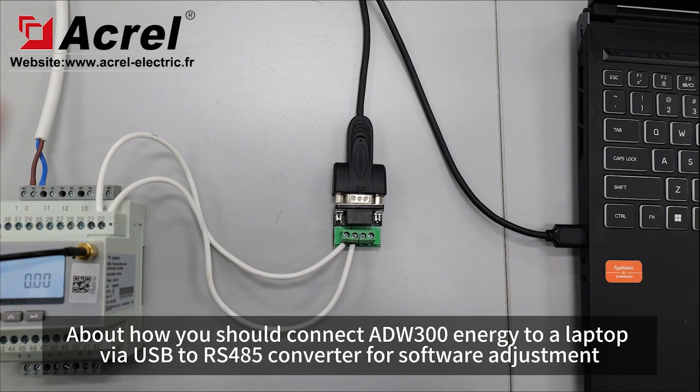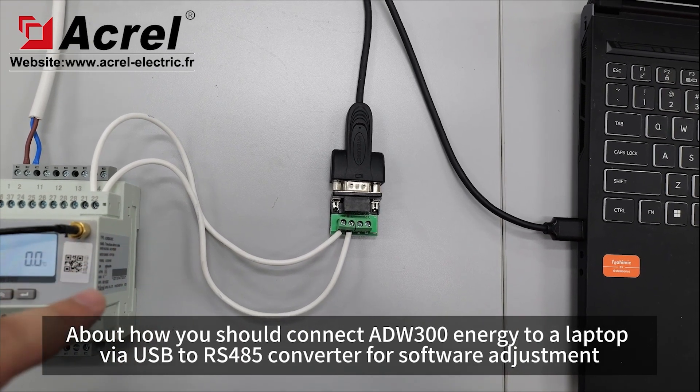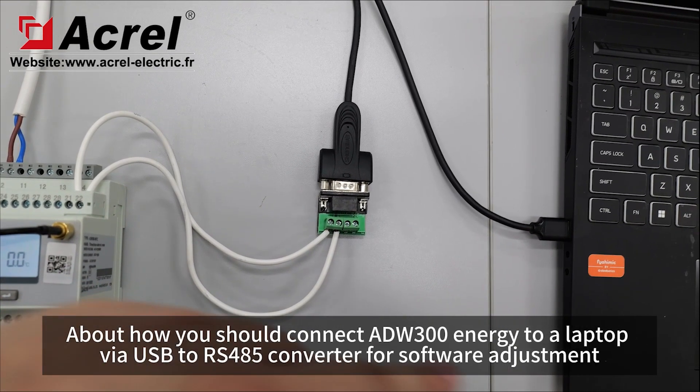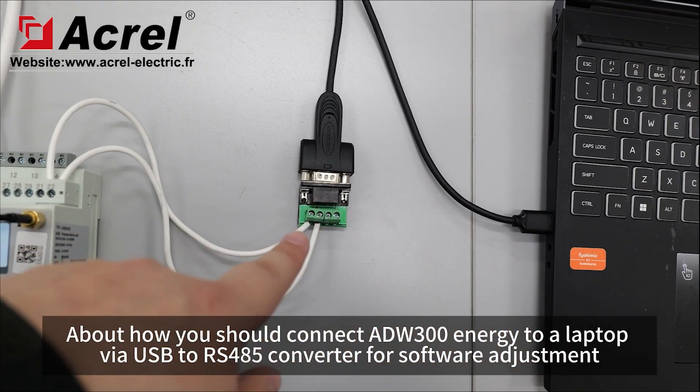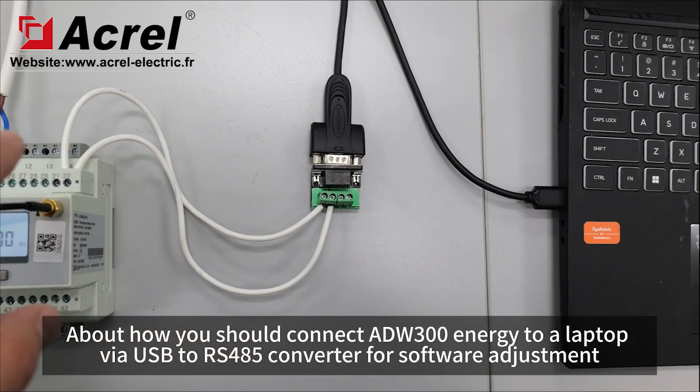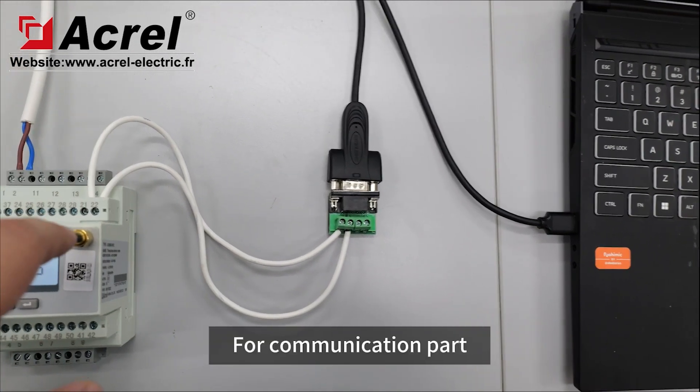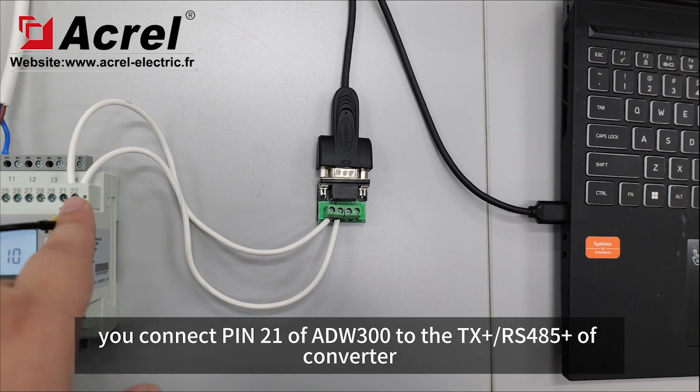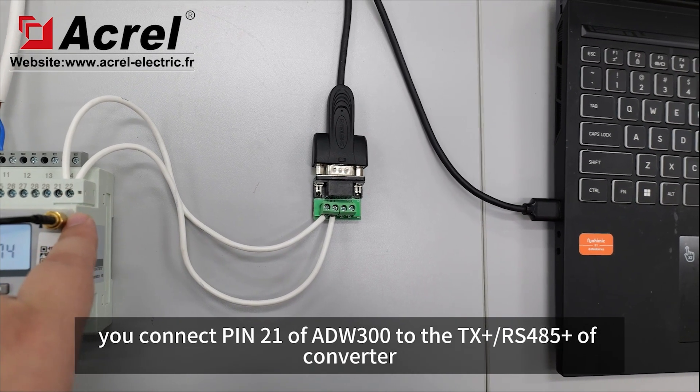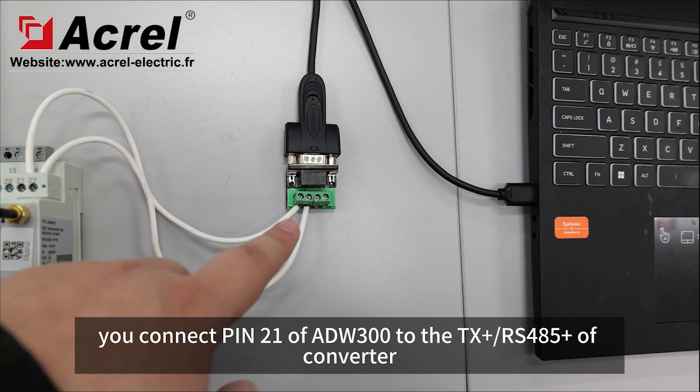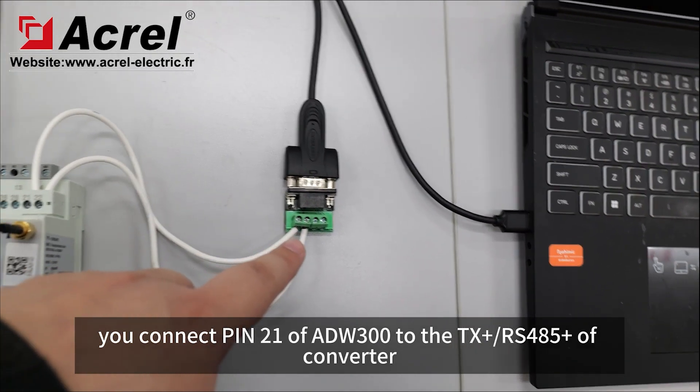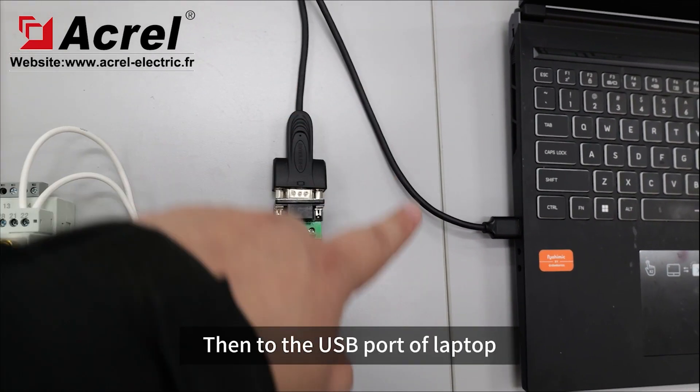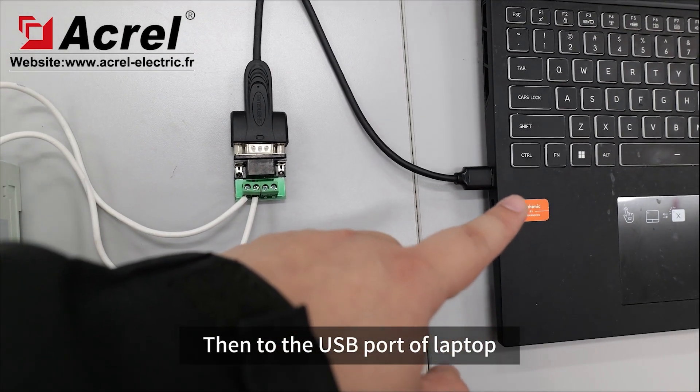For connecting ADW300 energy meter to a laptop with USB to RS-485 converter for software adjustment, connect pin 21 of ADW300 to the TX plus or RS-485 plus of the converter, then to the USB port of the laptop.